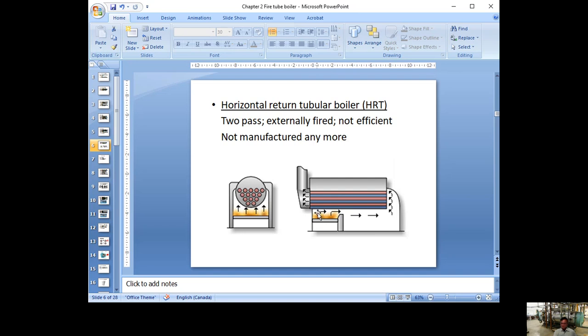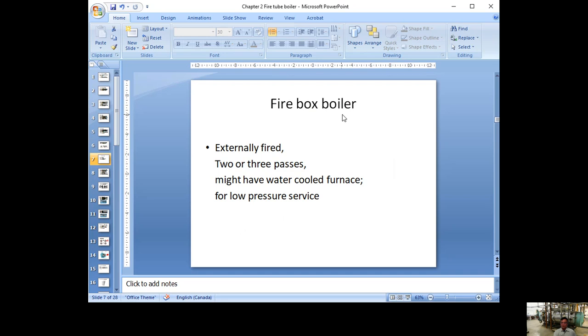They added one or two compartments — two to three passes — to make the flue gas turn around, improving efficiency. Sometimes they had water on one side of the furnace. But this kind of design was only good for low-pressure applications. They mostly don't make it anymore, but some are still around. About 10 years ago I went to inspect a federal government building at a border crossing, and in the basement they had a cast iron boiler from around the 1880s — still running.